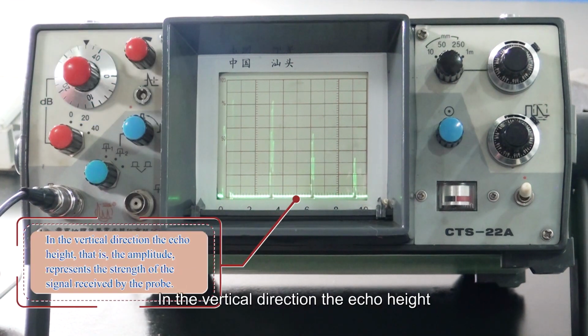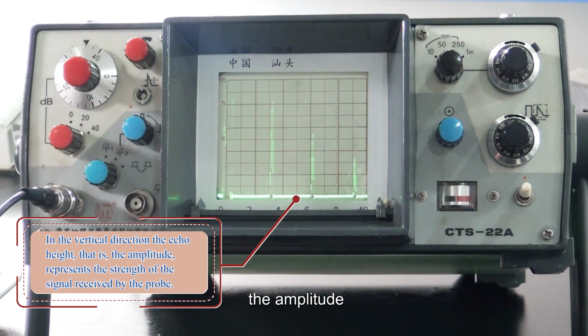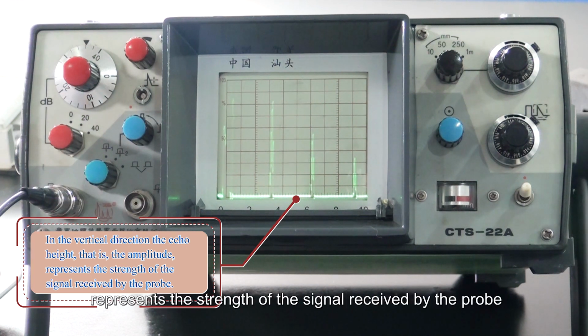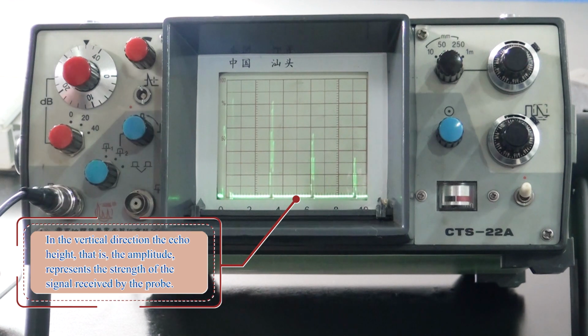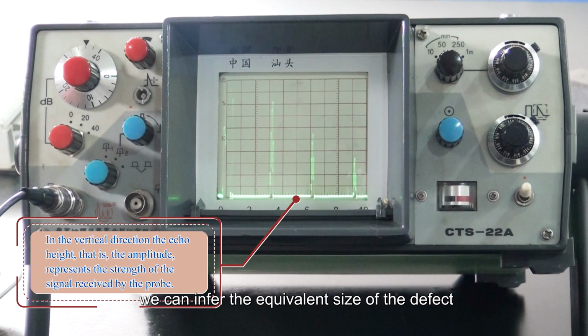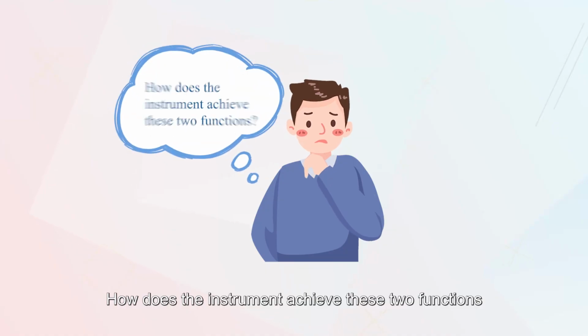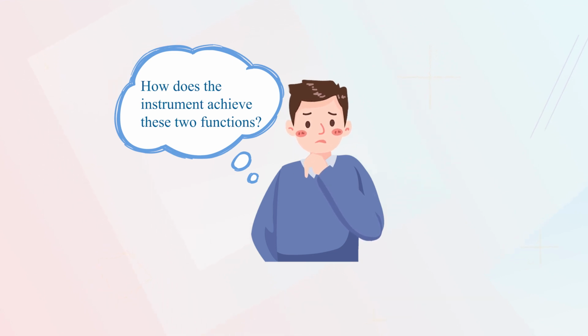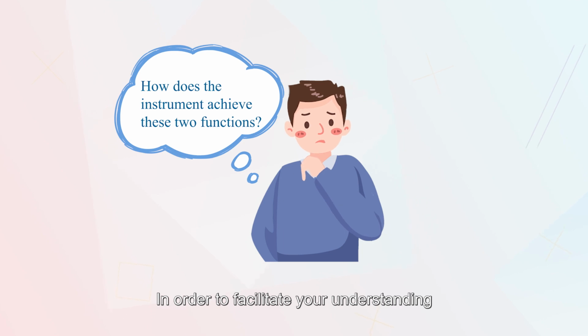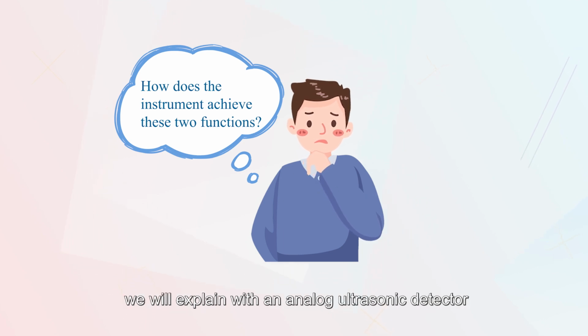In the vertical direction, the echo height, that is, the amplitude, represents the strength of the signal received by the probe. From this, we can infer the equivalent size of the defect. How does the instrument achieve these two functions? In order to facilitate your understanding, we will explain with an analog ultrasonic detector.